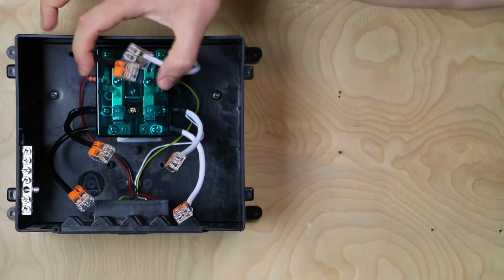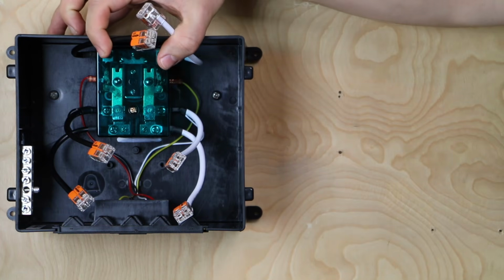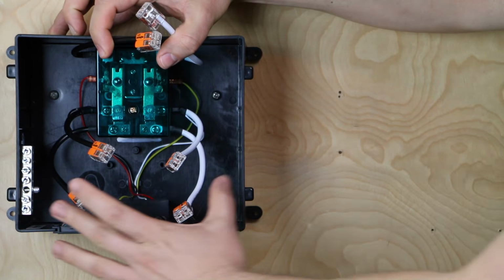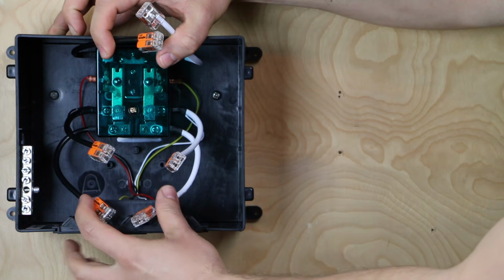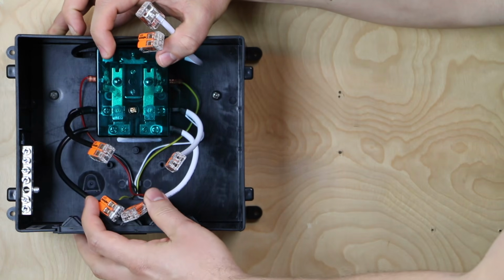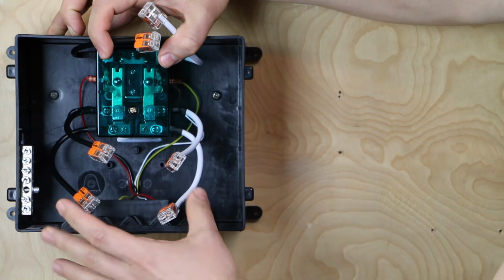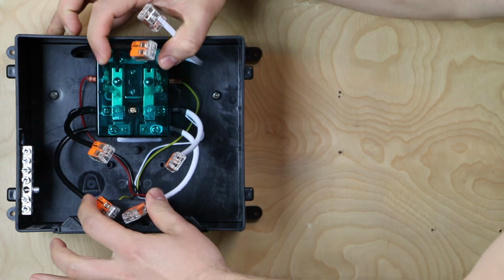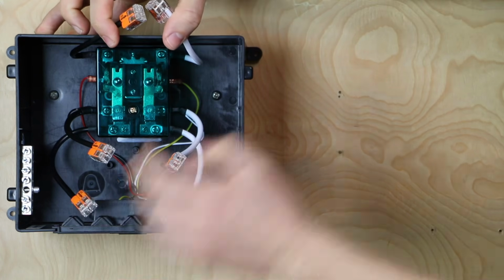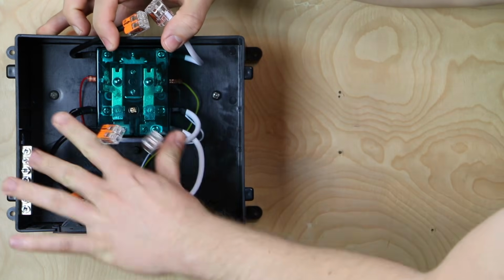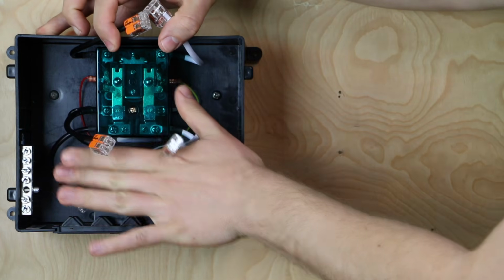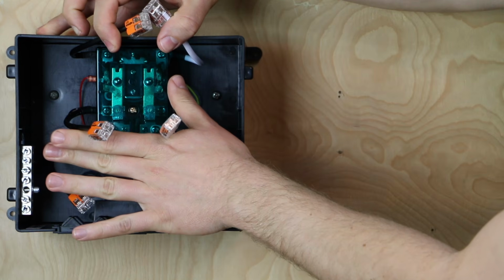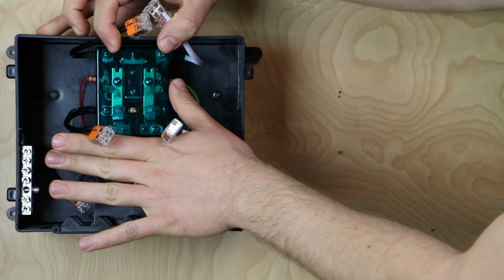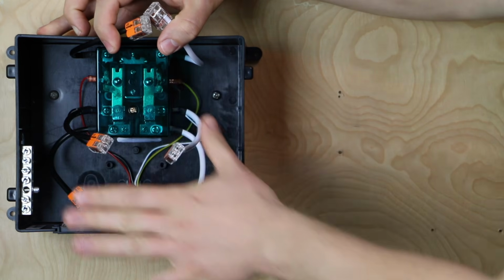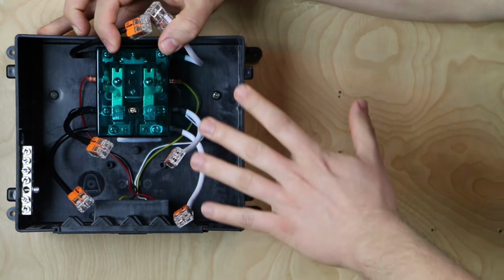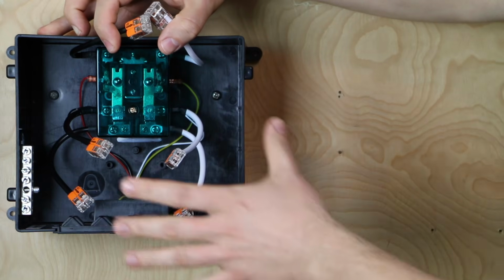Now, as far as the internals of the transfer switch, we've got a couple things going on here. Basically, these wires at the top are your output to your breaker panel, and these wires at the bottom are your default power source. At this time, power would run from these cords through the switch and out the top through these. Then your middle pair are actually kind of your dynamic source. This could be a generator that turns on, or this could be the power grid that turns on. There are multiple scenarios shown in the manual.